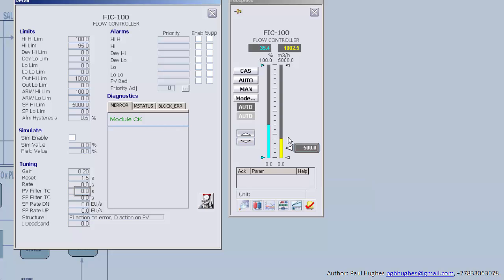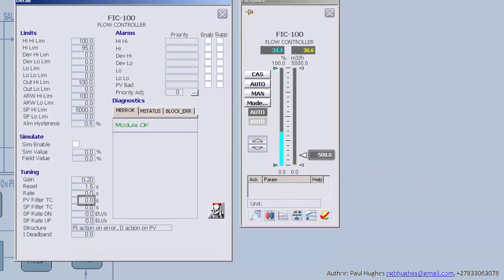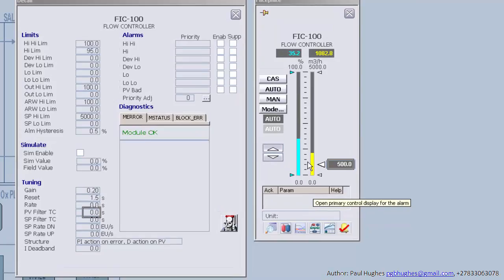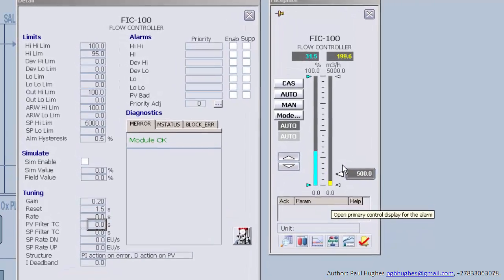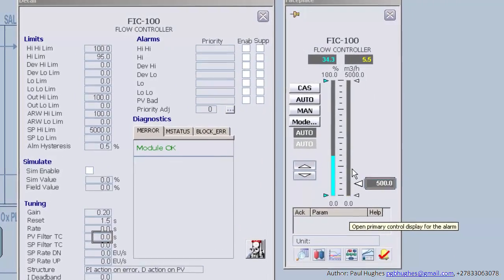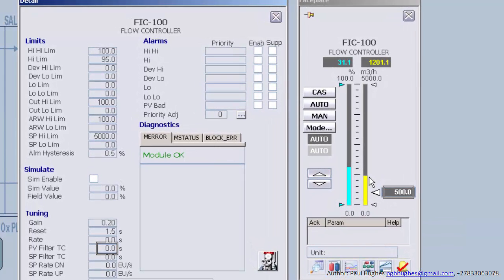So the question is, what options do we have, based on all of the other tools and methods that I've gone through, that we can address this? And this is possible. Basically what we need to do is first understand where this low range turn down becomes an issue for control, and what do we do at that point? Is there a fallback? Can we fall back to an estimated value?